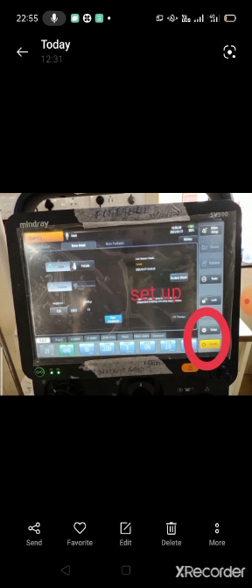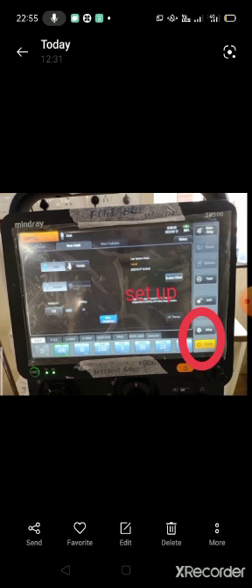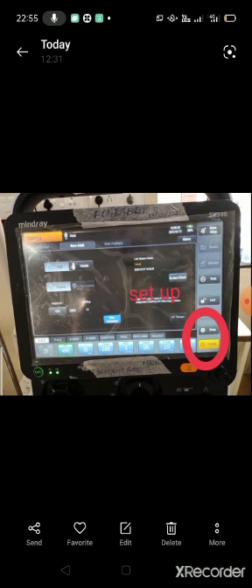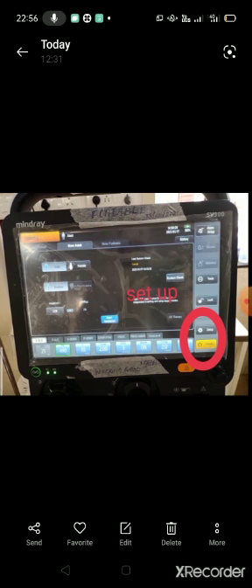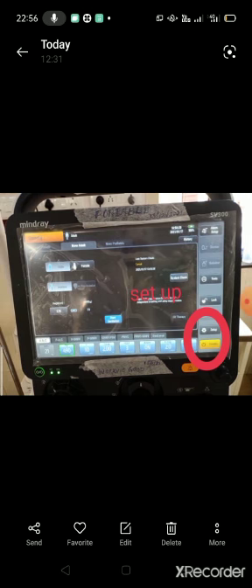So the next thing that you have to know is how to convert the ventilator to portable. I have already told, when you're connecting the ventilator in portable mode, you will get the oxygen from the cylinder. So you will be connecting the flow meter to the cylinder without water filled in the humidifier, and you will be connecting the tubings at the backside port, which I have shown earlier.